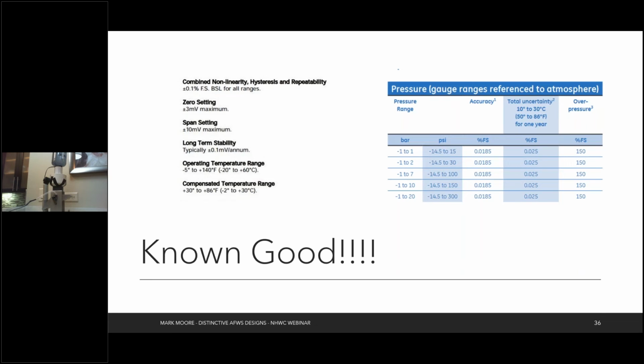I said known good, and I want to take a moment to focus on that a little bit. The PT specification that I showed you was 0.1% full scale error. Our known good we're going to use today in our example has specifications as shown on the right, and we'll look at the total uncertainty. Our total uncertainty for this calibration tool is 0.025% full scale. So our calibration device is actually, in this case, 5 times more accurate than our PT. And that's how we can calibrate, because we're taking something we know is very accurate, our PT calibrator, and we're going to use that to simulate pressure against our PT.